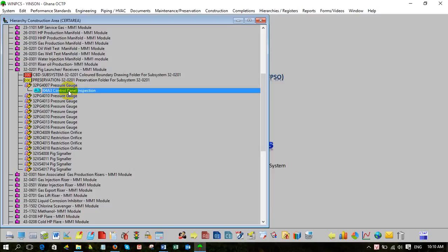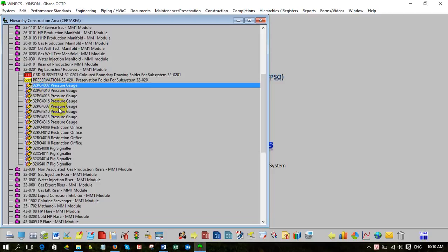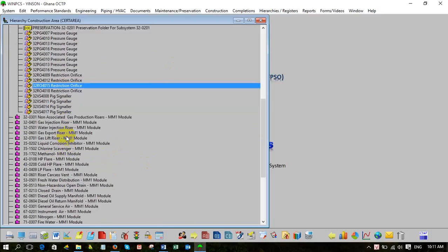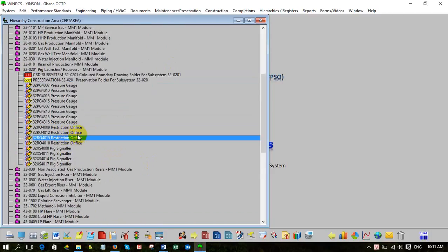Sometimes one equipment I can have 2 ITR. Doesn't mean every equipment has ITR. Some equipment, only ITR. For example, my thermowell. Thermowell, no ITR, because the ITR will sit on the transmitter. Because thermowell is welded to the pipe, so no need for ITR. That one will be covered under piping. So when you put a transmitter, then the transmitter has ITR. So when you look, sometimes you ask, hey, how come there's no ITR for thermowell? For example, like RO, you need ITR.